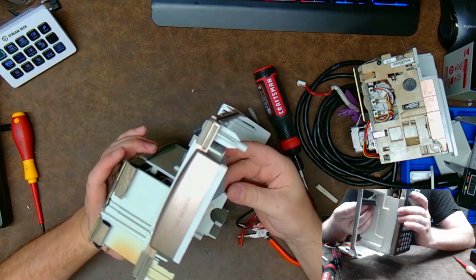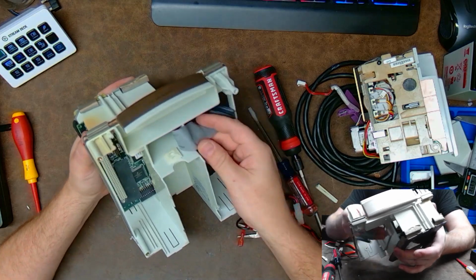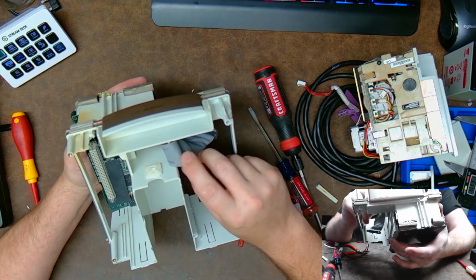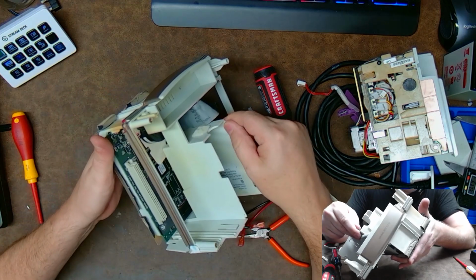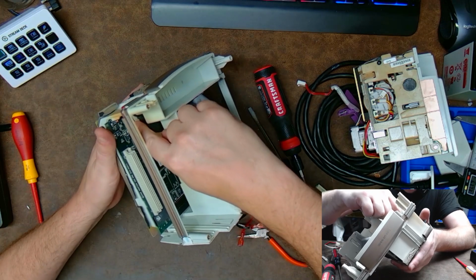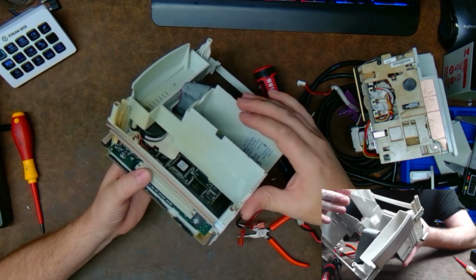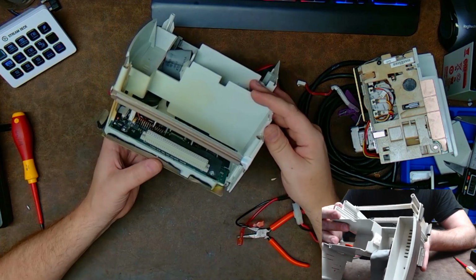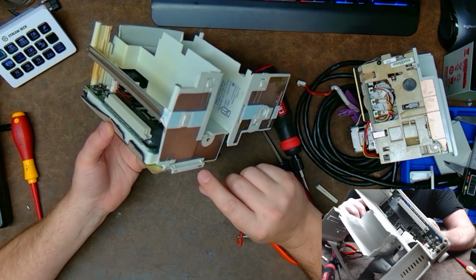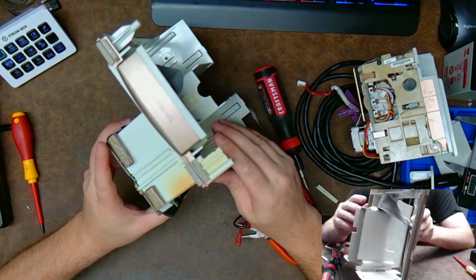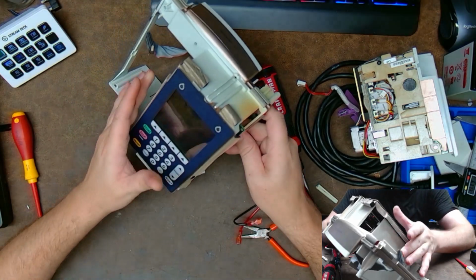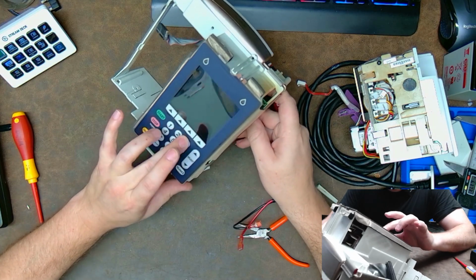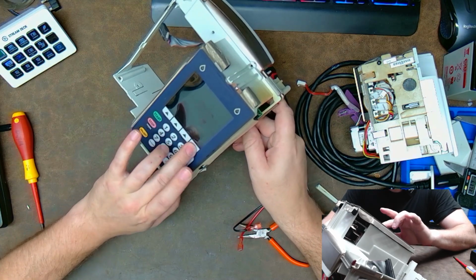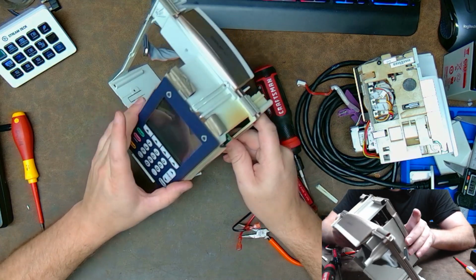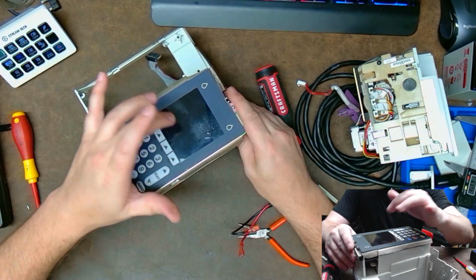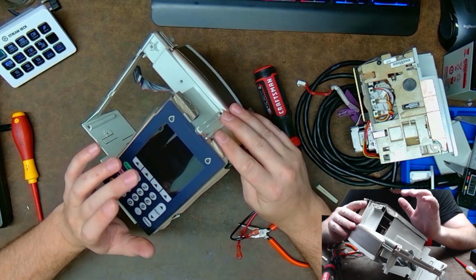So anyway, that ribbon cable, got to be very delicate. Sometimes it will get pinched, and if it gets pinched, especially when putting it back together, you will create problems for later on in life. It's got an alarm speaker in here and nothing much major. That can be pulled apart by some little tabs and a little screw right here. Regular membranes, check for cracks. Always check for cracks.